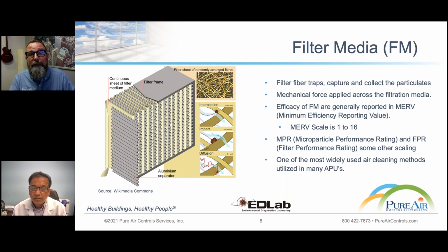Because filter media is restrictive, the airflow or ventilation, which is so important during this pandemic, is going to be restricted itself. So you'll have a harder time controlling temperature and humidity in the zones the HVAC system services. We want to be very careful not to just put a higher rated filter in your air handler unit unless you check how that unit or its controls are designed.